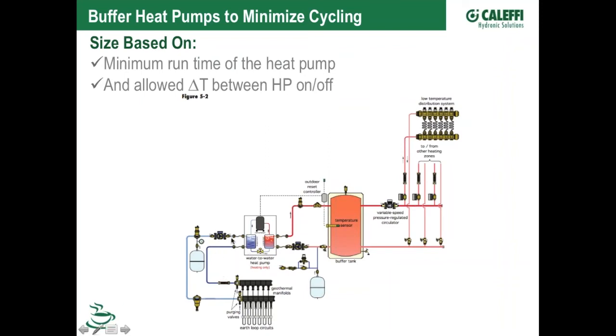Yeah, because the fluid's going to change temperature in this, in the heating and the cooling mode. If this is a heating and cooling application, we need an expansion tank in there when we heat fluids because they expand, but the opposite happens when we chill water. So if we put, let's say, 10 pounds of system pressure in there and we chilled this, we started using this as a chiller and this loop field temperature started going down, the pressure is going to go down. So this expansion tank works both ways in a system.